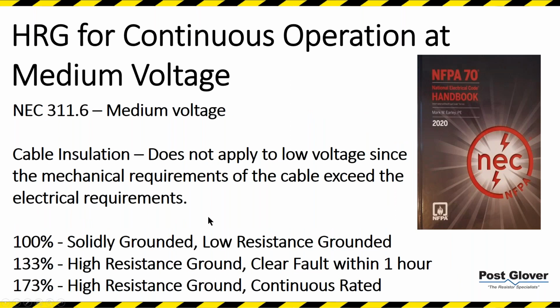So let's go over the NEC requirements for cable at medium voltage. This is NEC 311.6. It has to do with the cable sizes depending on what grounding operation you're using. So for 100%, you're getting solid ground or low resistance ground, and you're using your standard wires. This is just a visual aid for people. I'm not the greatest artist, so forgive me, this is not to scale. So that's going to be low resistance ground, or solid ground.